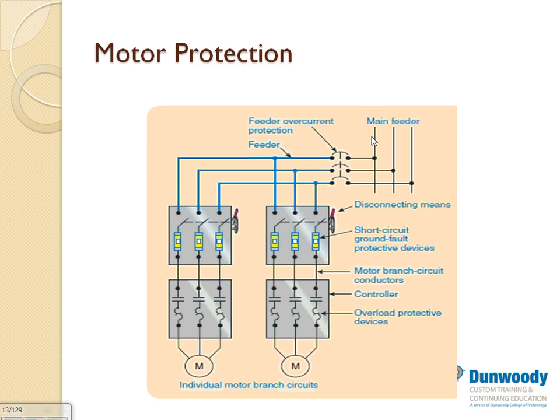Here's what we're talking about, guys. You grab your feeders. You look at your feeders right here. How are you going to size your feeders? How are you going to size the branch circuit? These are your branch circuit that's coming in here. All this, you're going to take 1.25 and multiply it by the full load current. I want to use the word full load current. This is why it's very important, guys, to know the full load amp or full load current of a motor, because based on that, you can size the conductors coming to it, the short circuit. You're going to size the branch circuit motor conductors, which is the same here and here, controller, and overload protective device. The overload protective device.